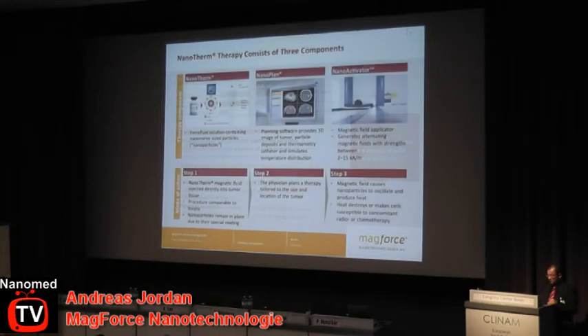And the third component is the magnetic field applicator. It's called the nanoactivator. It looks a little bit like a CT scanner or an MRI scanner, but it's quite different because it generates this AC magnetic field, which matches nicely with the particle size distribution, which has been developed as an optimum of power absorption. So you need a minimal amount of particles to get the heat into the tissue. And as you can see, the positioning of the patient is quite simple, and you don't need a fixation of the patient. So every region of the body can be treated with this method.